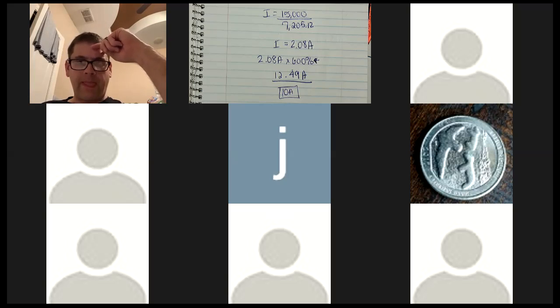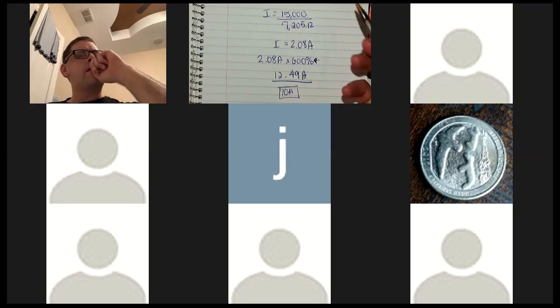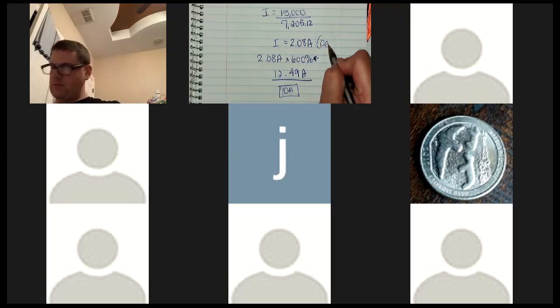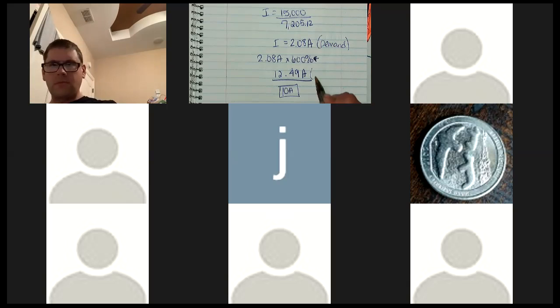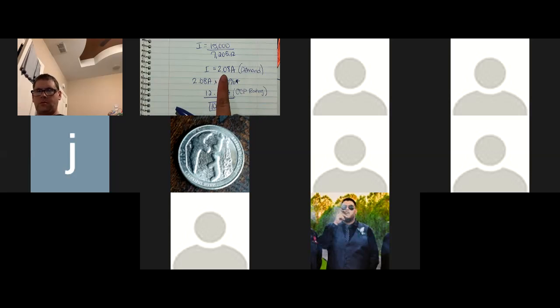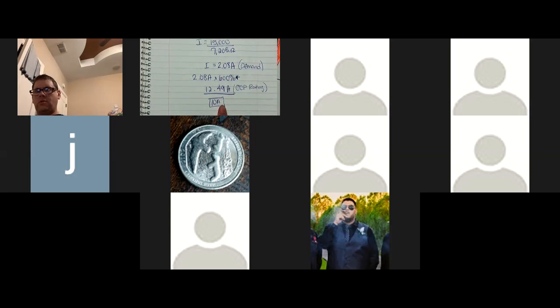Additional standard ratings, so do we size it up or down? I would go with 10 amps because, like we said before, this is your demand right here, this is with your overcurrent protection rating. So the question is, would you want it to trip at the 12 or the 10, the 15 or the 10? Well, my amperage is only pulling 2.8, 2.08, so I'm going to go with the 10.